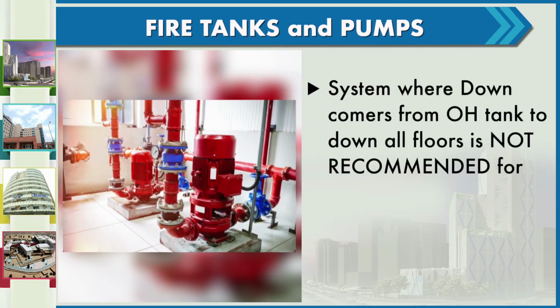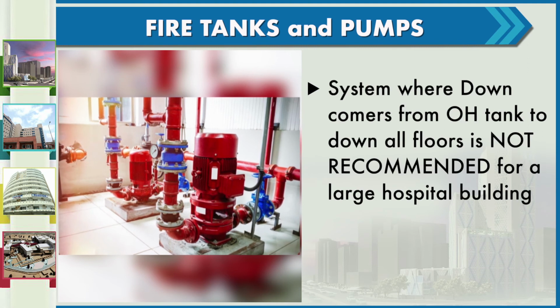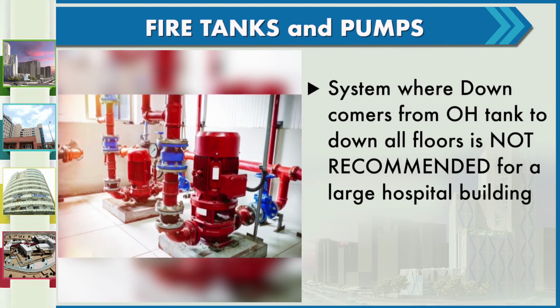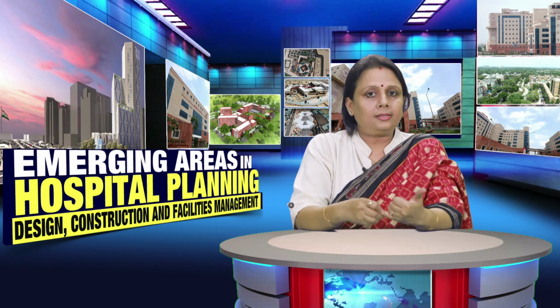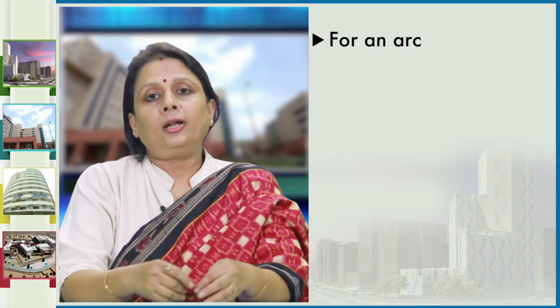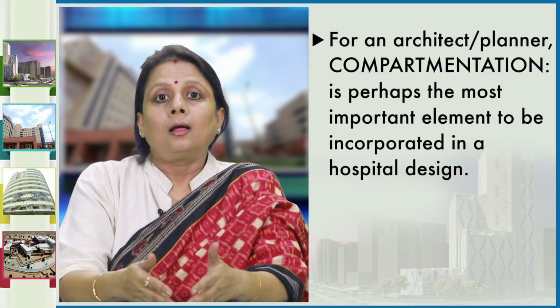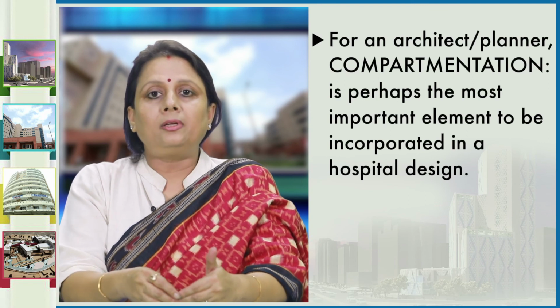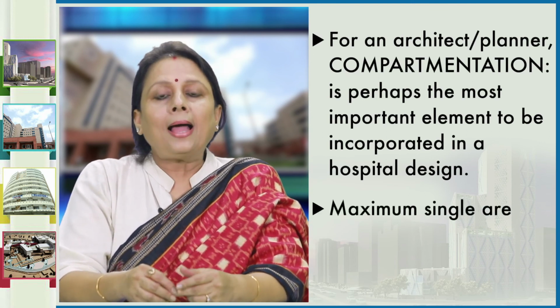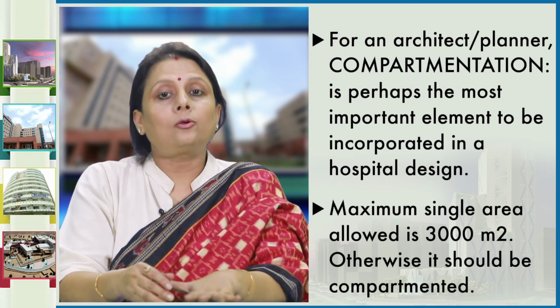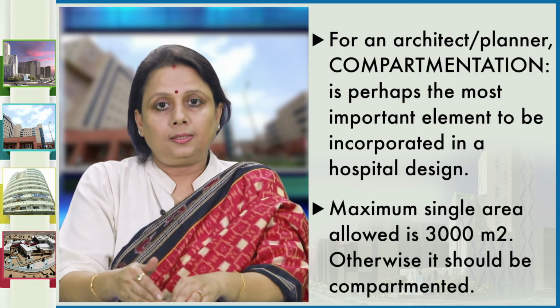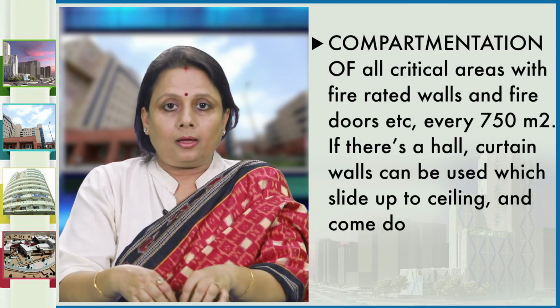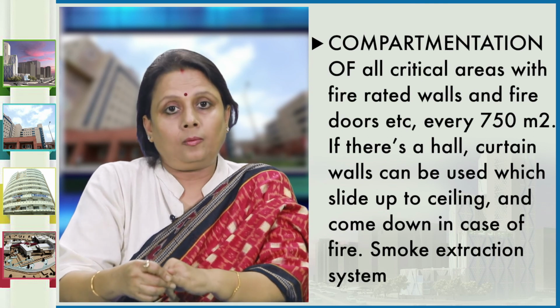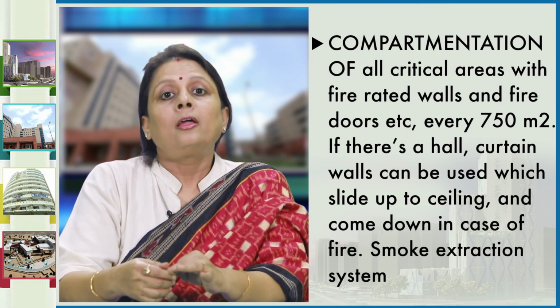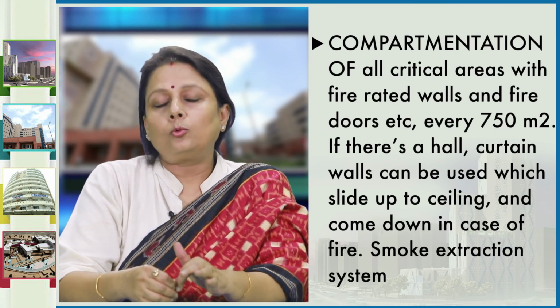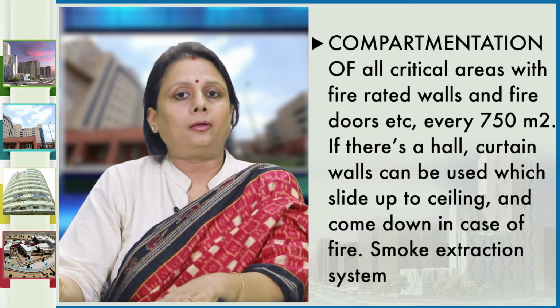There is also a system where downcomers from the overhead tank come down to all the floors, but this is not recommended for a large hospital building. If the basement is over 200 square meters in size, sprinklers are to be provided there too. For an architect, planner or designer, compartmentation is perhaps the most important element to be incorporated in a hospital design. Maximum single area allowed is 3000 square meters, otherwise it should be compartmented. Compartmentation of all critical areas with fire rated walls and fire doors etc. every 750 square meters. If there is a hall, curtain walls can be used which slide up to the ceiling and come down in case of a fire.